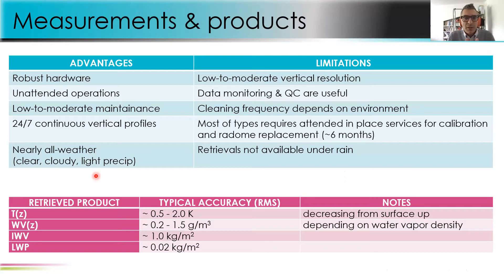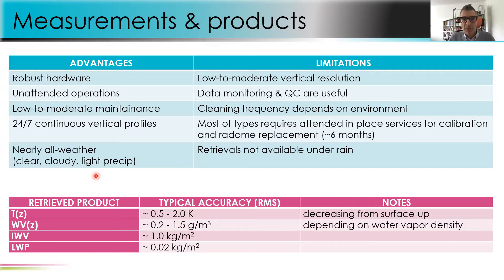Advantages of microwave radiometers include robust hardware, unattended operations, low to moderate maintenance, and continuous vertical profiles in nearly all weather — clear, cloudy, and up to light precipitation. Limitations include low to moderate vertical resolution, the need for data monitoring and quality control to check for instrument drift, and occasional cleaning of the antenna radome. Most types require attended in-place service for calibration and radome replacement about every six months. Retrievals are not available under rain.